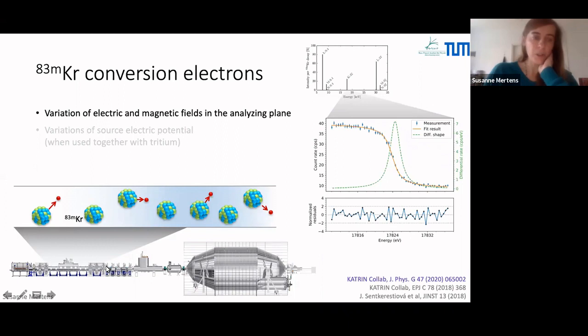So we use the krypton source in its gaseous form, and we just insert it into the windowless gaseous tritium source, and we do that before actually inserting tritium. So there is krypton only, and by measuring then the position of the line and also the width of the line, we can deduce back the electric potential and the magnetic field in our spectrometer, in the center of the spectrometer, which we call the analyzing plane.